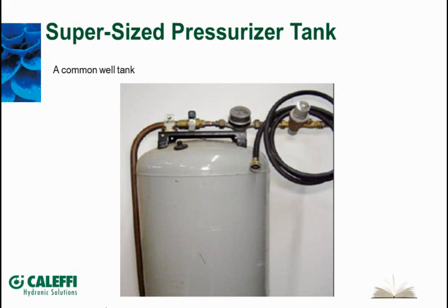Here's one. I think that's a 20-gallon well tank. I added one more component to this one when I built it, and I put a little water meter on here. So what I can do with this, if I'm filling a system for the first time and I want to know how much fluid it's going to take, because I'm going to have to come back the next day and put glycol on it, maybe a solar system where I'm going to flush it out, you can put that meter on there and then just see, it's a really accurate meter. It'll read down to about 1/10 of a GPM, so you can see how much fluid goes into the system.